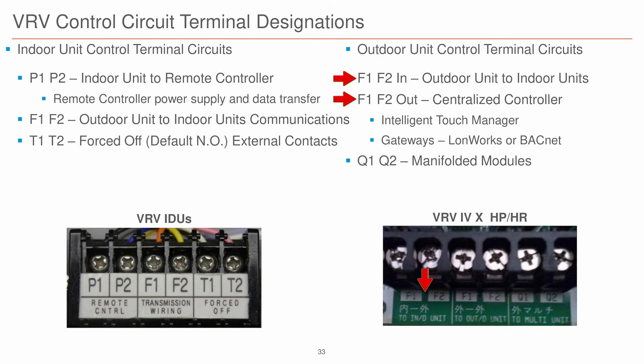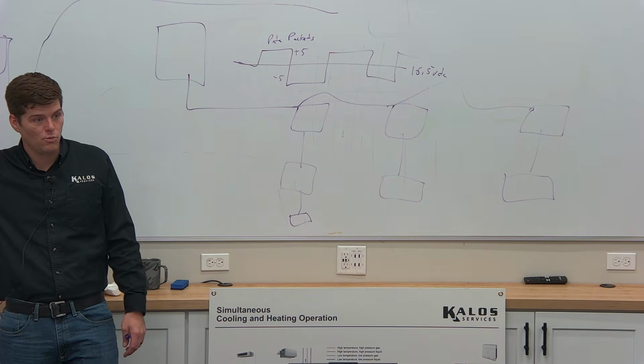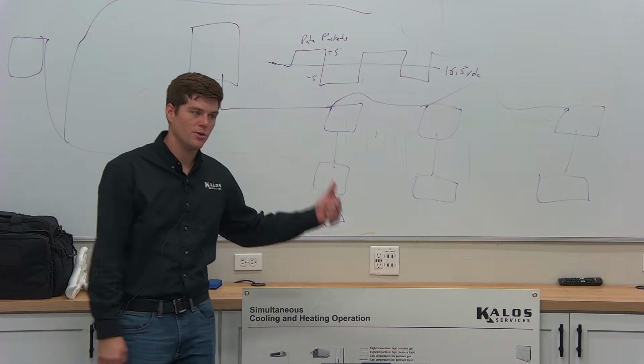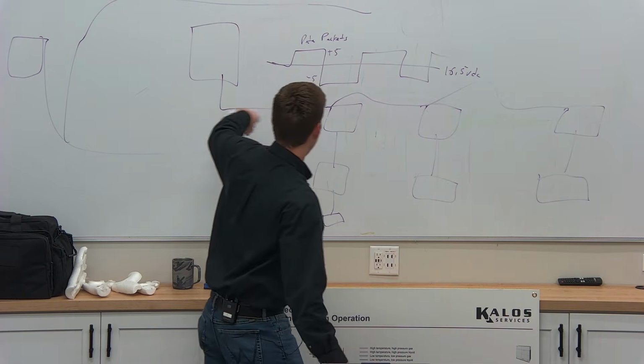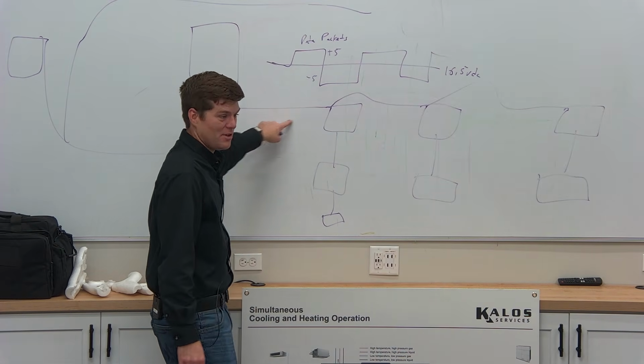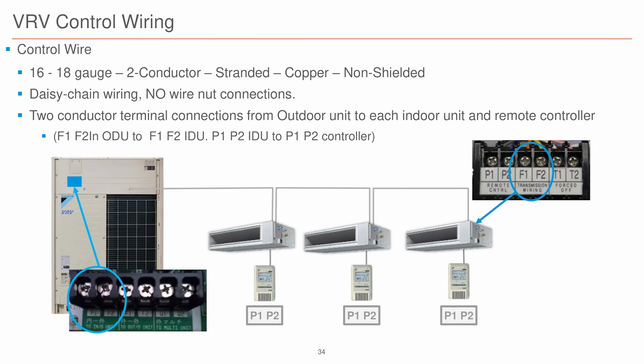So you have two sets of wires landed if you have another fan coil to go to on that indoor unit. And then outdoor units connected together, Q1, Q2, and then the F1, F2 out, that goes to like a centralized controller, so we can have a touchscreen controller that actually connects to 13 different outdoor units in the entire building. And I can see all the indoor units from one controller. That would be where it connects to on the outdoor unit. And then that in itself is still connected to this communication line. But let's not get bogged down in that. I'm going to teach a service class just on that, but this is the brief overview, guys.